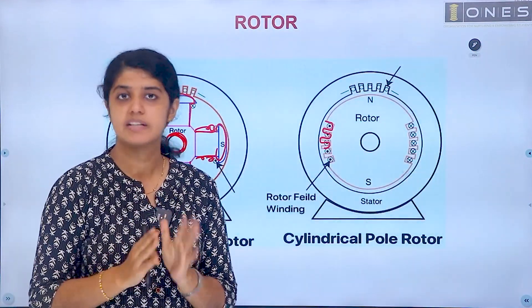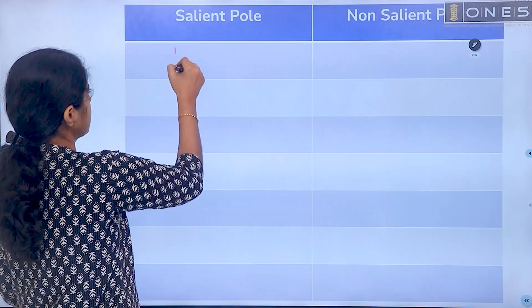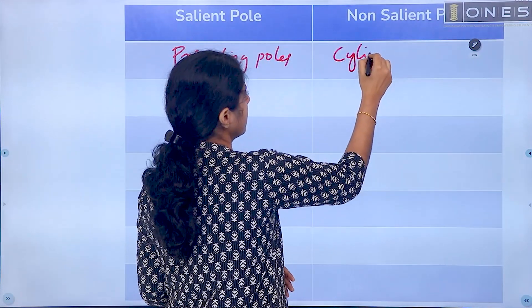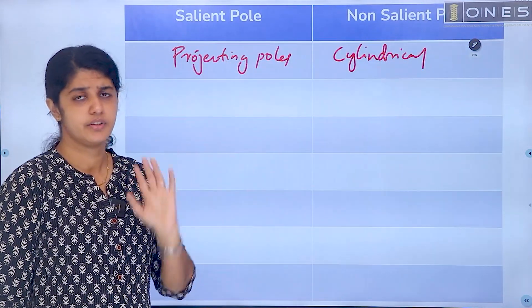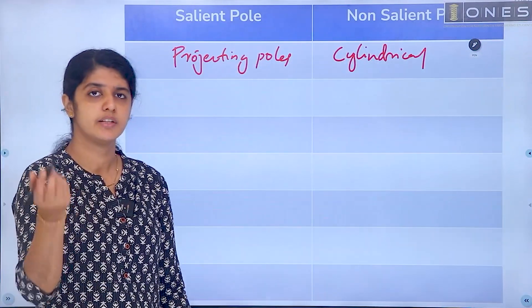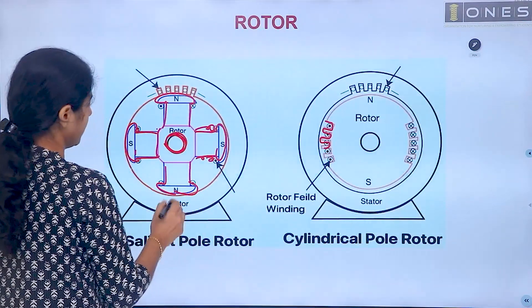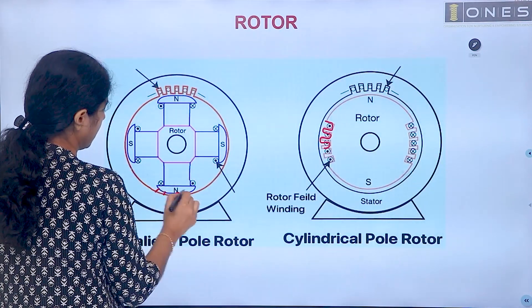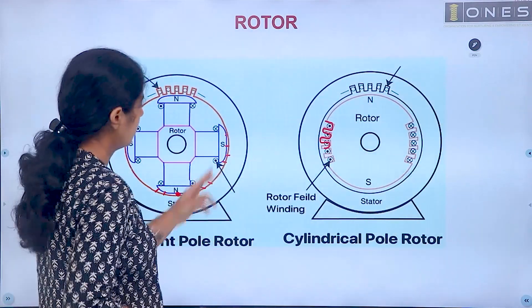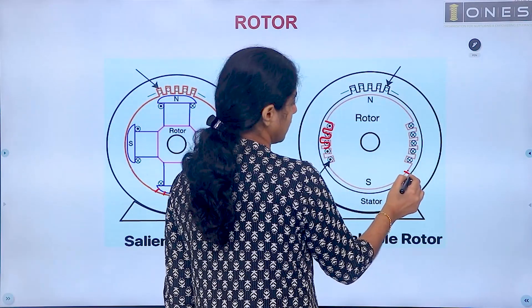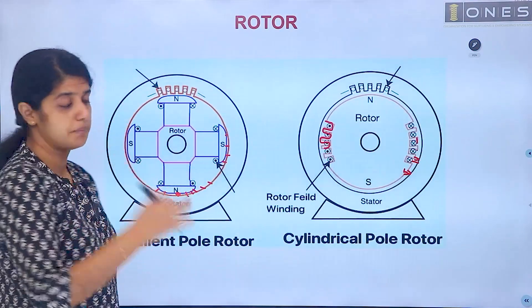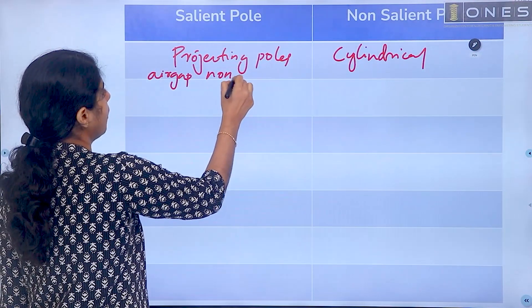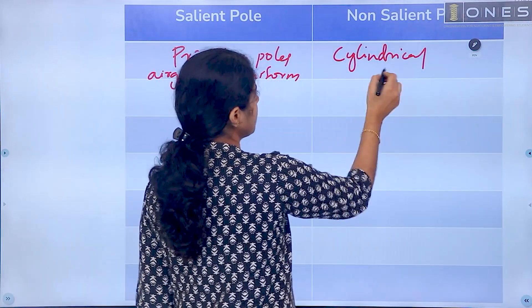First, let's compare the structures. In the salient pole, we use projecting poles, while in the non-salient pole, we use the cylindrical structure. Regarding the air gap: in the salient pole machine, the air gap is non-uniform, whereas in the case of non-salient pole, the air gap is uniform.